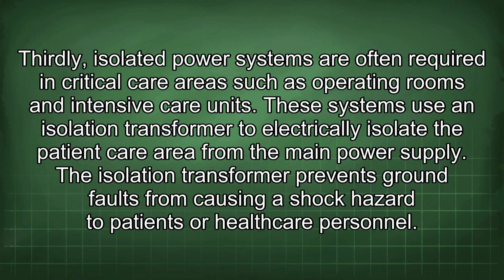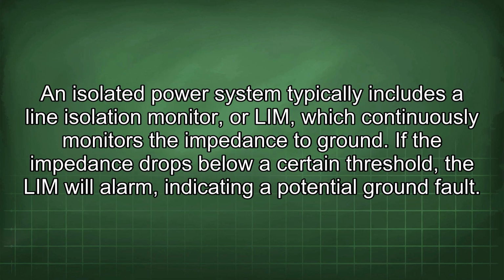Thirdly, isolated power systems are often required in critical care areas such as operating rooms and intensive care units. These systems use an isolation transformer to electrically isolate the patient care area from the main power supply. The isolation transformer prevents ground faults from causing a shock hazard to patients or healthcare personnel. An isolated power system typically includes a line isolation monitor, or LIM, which continuously monitors the impedance to ground. If the impedance drops below a certain threshold, the LIM will alarm, indicating a potential ground fault.